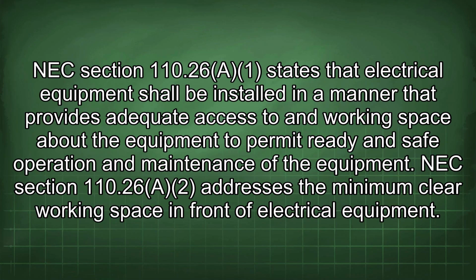NEC Section 110.26(a)(1) states that electrical equipment shall be installed in a manner that provides adequate access to and working space about the equipment to permit ready and safe operation and maintenance of the equipment. NEC Section 110.26(a)(2) addresses the minimum clear working space in front of electrical equipment.